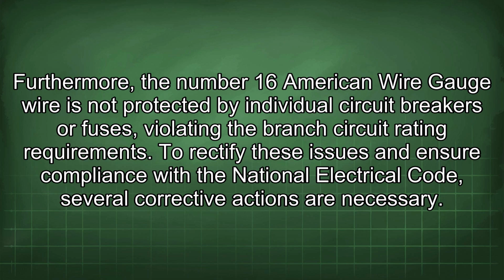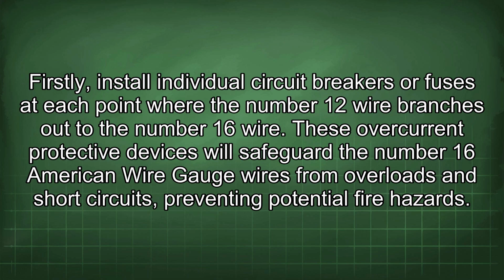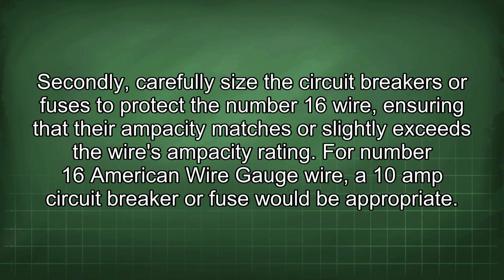Furthermore, the number 16 American wire gauge wire is not protected by individual circuit breakers or fuses, violating the branch circuit rating requirements. To rectify these issues and ensure compliance with the National Electrical Code, several corrective actions are necessary. Firstly, install individual circuit breakers or fuses at each point where the number 12 wire branches out to the number 16 wire. These overcurrent protective devices will safeguard the number 16 wires from overloads and short circuits, preventing potential fire hazards. Secondly, carefully size the circuit breakers or fuses to protect the number 16 wire, ensuring that their ampacity matches or slightly exceeds the wire's ampacity rating. For number 16 wire, a 10 amp circuit breaker or fuse would be appropriate.